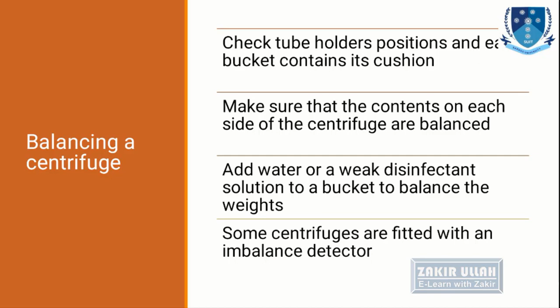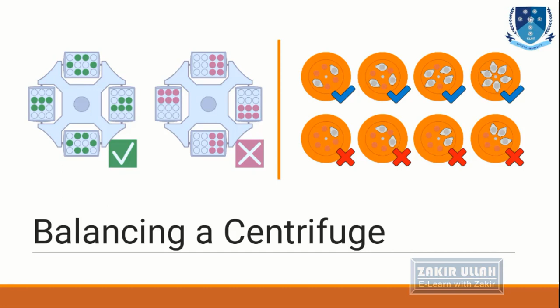This is a picture which shows how to balance a centrifuge. On our left side, we have an image of a swinging bucket centrifuge in which different samples are shown, showing how to balance different samples in a swinging bucket centrifuge. This is a good example. This is a good balance, and this is a bad practice, and this is unbalanced in this image. And we can see on the right side there is a fixed angle centrifuge, and different samples are put in Eppendorf tubes, and then they are shown as balanced and these are shown as imbalanced. These are the different types of centrifuge with their balancing mechanism.